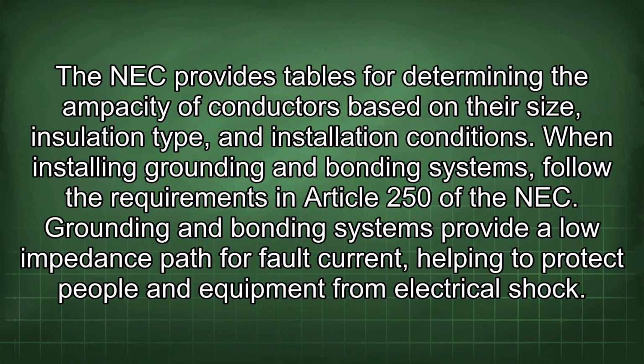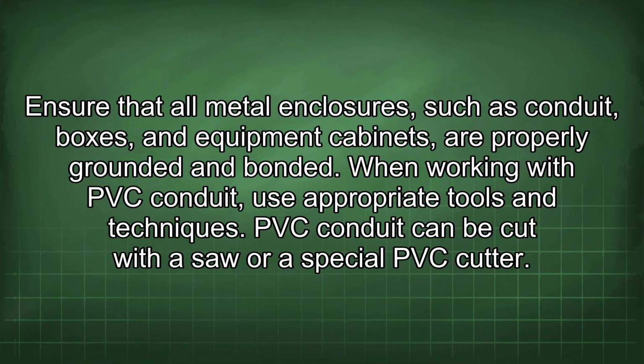The NEC provides tables for determining the ampacity of conductors based on their size, insulation type, and installation conditions. When installing grounding and bonding systems, follow the requirements in Article 250 of the NEC. Grounding and bonding systems provide a low impedance path for fault current, helping to protect people and equipment from electrical shock. Ensure that all metal enclosures, such as conduit, boxes, and equipment cabinets, are properly grounded and bonded.